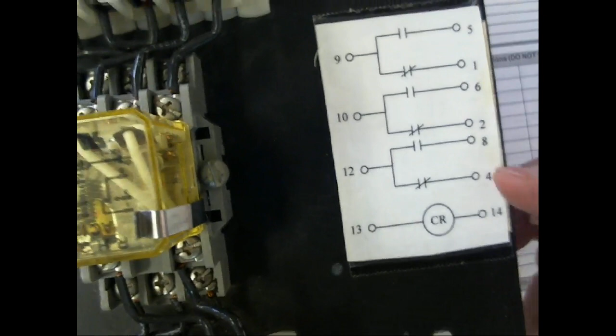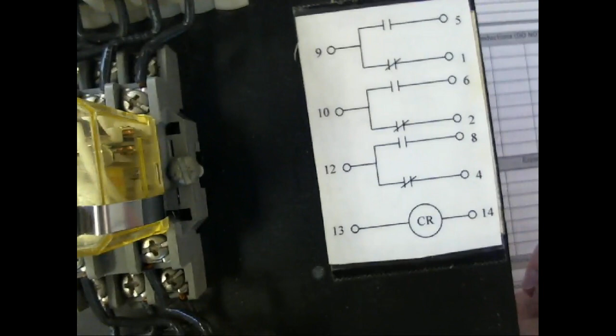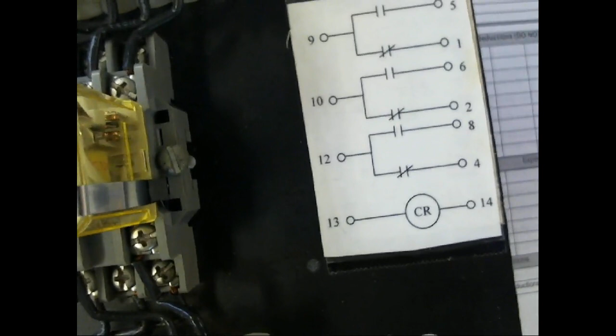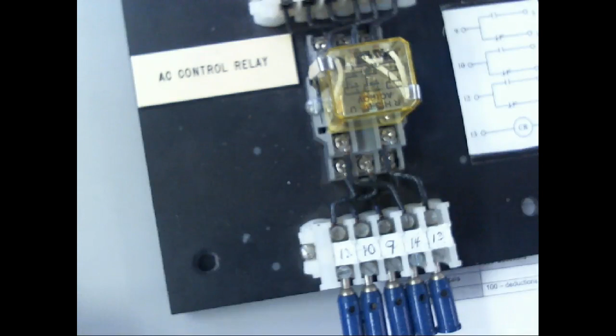So instead of me using two switches - and we have people do this, they'll use 9 to 1 for their normally open and 10 to 2 for their normally closed - it works fine, but what you've done is sacrificed 2 poles to get what I could have done with 1. Because on my diagram over there on L1, these two contacts are connected together anyway. So instead of using 2 of my poles for something I could do with one, we can't always do that - they've got to have a common, right? They got to have a common connection.